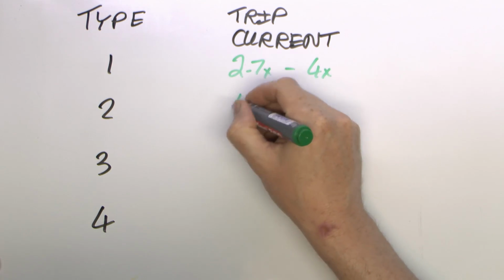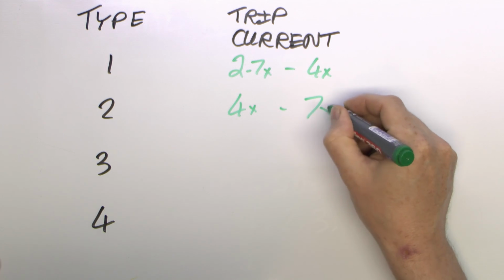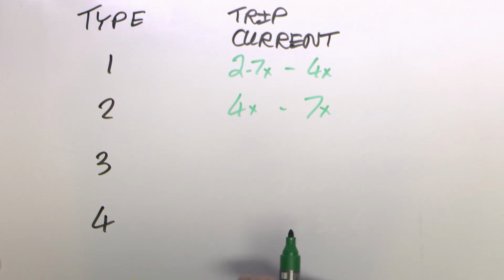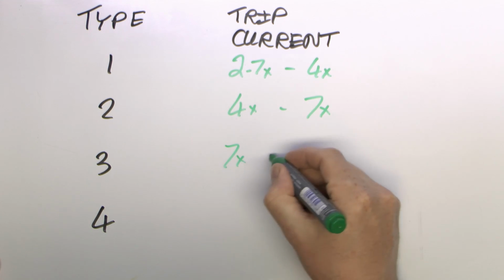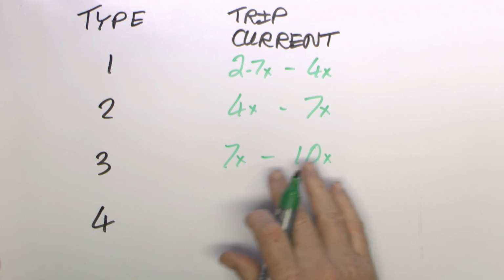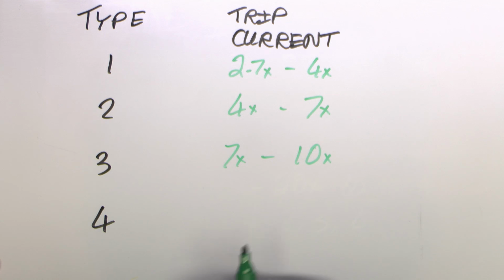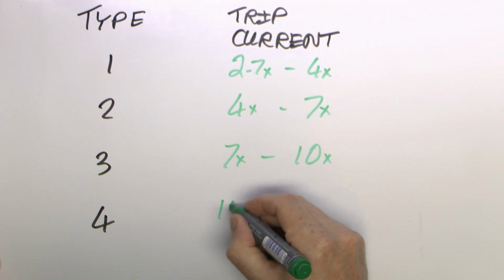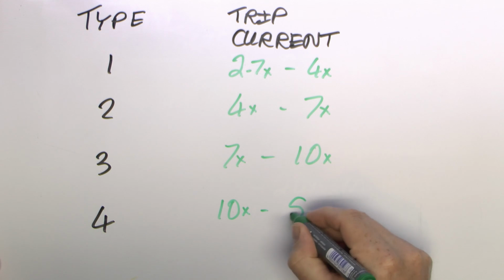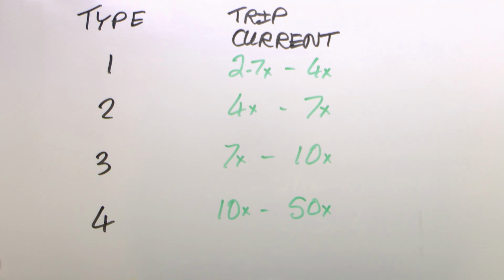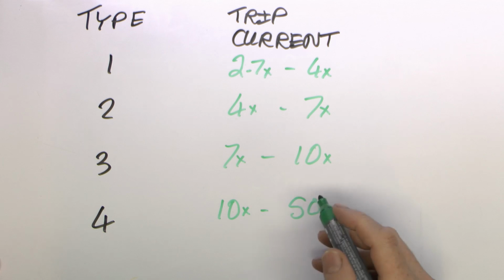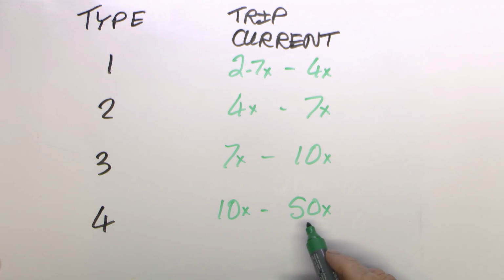The type 2 is somewhere between 4 times and 7 times, and you might say that's in the general area of a type C, although again the numbers are slightly lower. The type 3 was 7 times to 10 times, so again that's still in the range of the current type C one. And the type 4 is somewhere between 10 times and unfortunately 50 times the rated current. Now type 4s are fairly uncommon, and if you do actually find those, it's well worth getting the actual specifications for that particular one from the manufacturer, because they don't all go up to 50 times. Some of them actually are quite a lot lower than that.